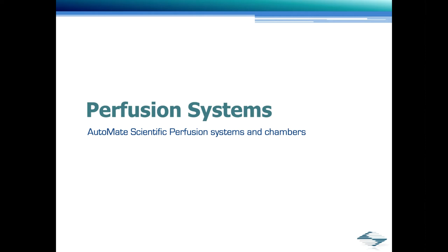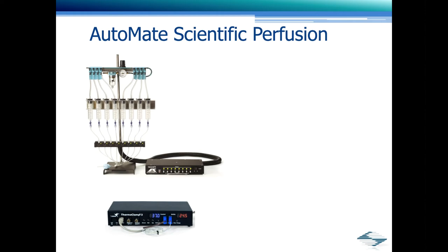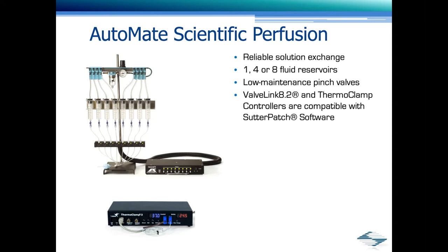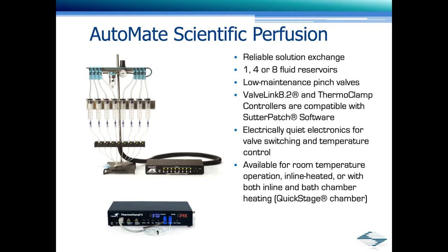No electrophysiology setup is complete without a perfusion system. It could be as simple as a manually controlled reservoir or a more complex multi-reservoir computer controlled system. Sutter offers the popular perfusion systems and bath chambers made by Automate Scientific. Features include reliable solution exchange. It's available one, four, or eight reservoirs. Low maintenance pinch valves. The ValveLink and ThermoClamp controllers are compatible with our Sutter Patch software. The controllers are electrically quiet. And it's available for room temperature operation, inline heated, or with both inline and bath chamber heating.